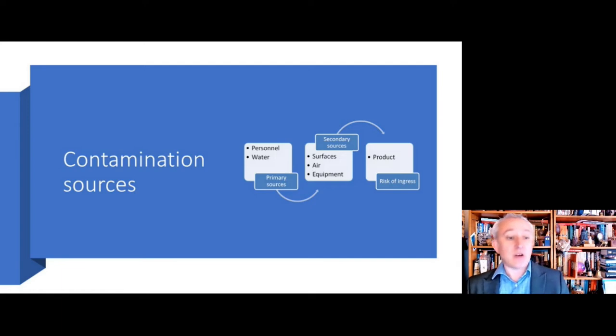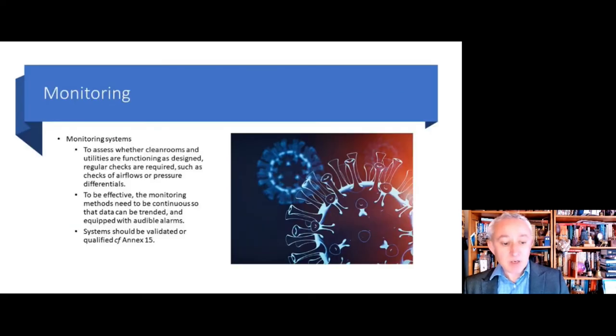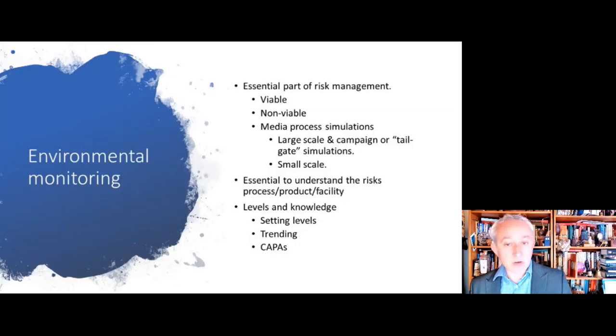So that's fairly broad contamination control introductory stuff. Let's go to environmental monitoring. Monitoring in the environment is one of the key monitoring systems in the pharmaceutical process. There's physical monitoring systems such as pressure, airflow, temperature, and humidity. Checks to see whether clean rooms and utilities are functioning as designed. These are all really important because they're key control factors in terms of the likelihood and distribution of microorganisms.